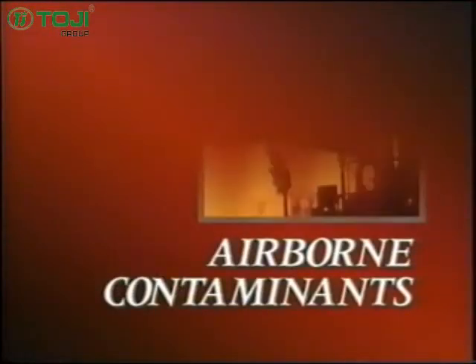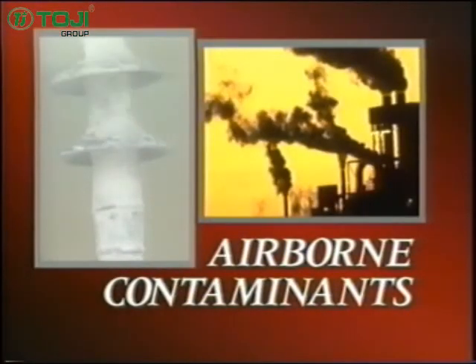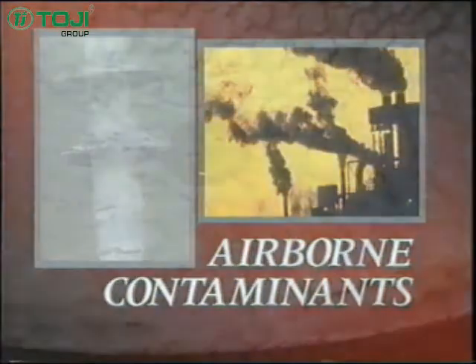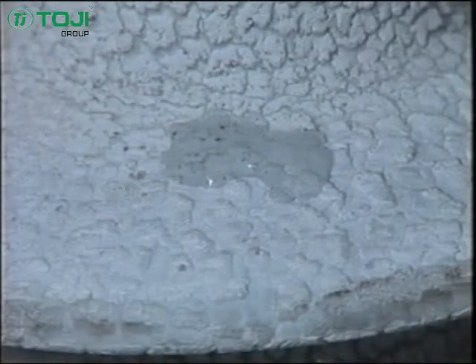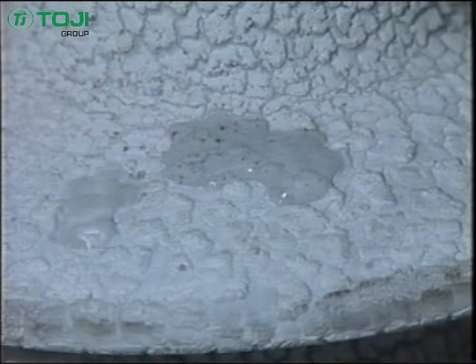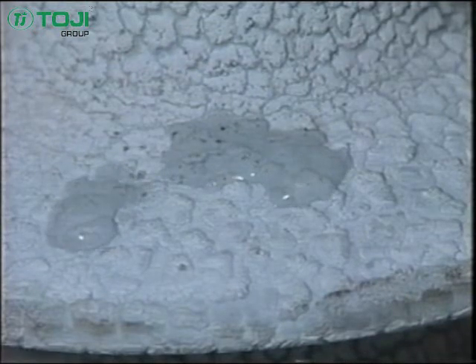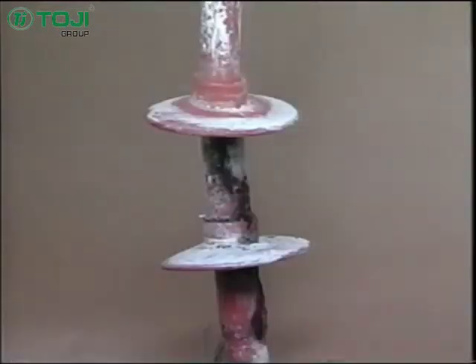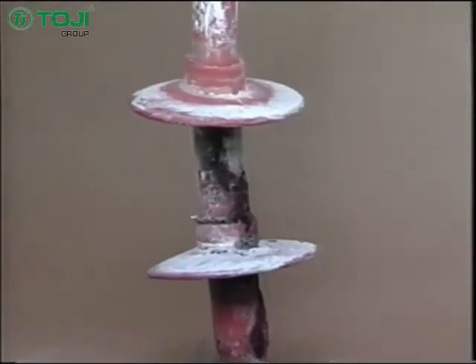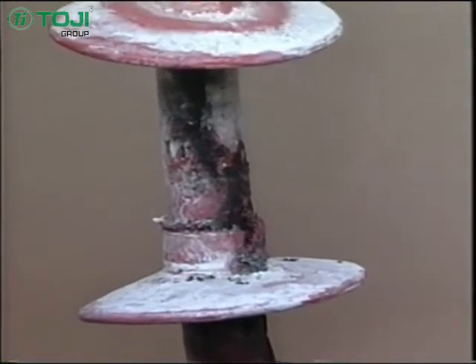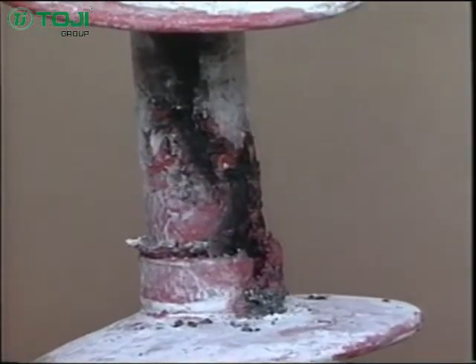Third are the airborne contaminants and pollution that build up and eat away at the surface structure. When the surface is no longer uniform, certain areas actually build up with moisture, while other surface areas have no moisture and form dry bands. The current flows along the moisture surfaces relatively easy, but when the current hits the drier spots, it jumps or arcs over the dry spots or dry bands. These small arcs further degrade the insulator, eventually leading to material erosion, followed by total failure.